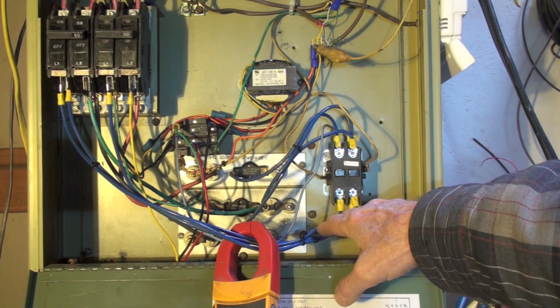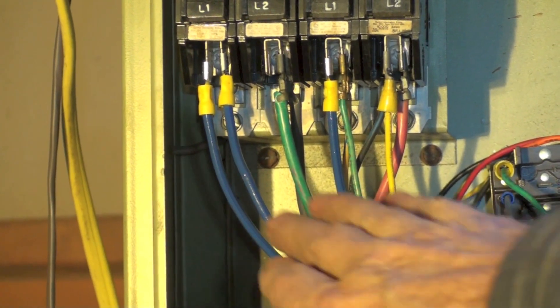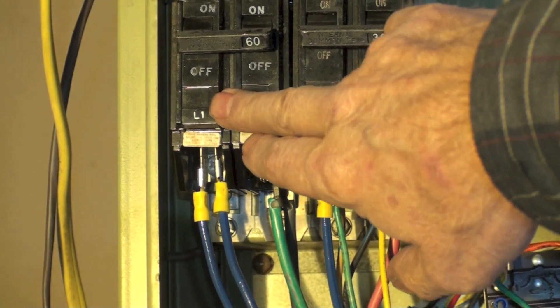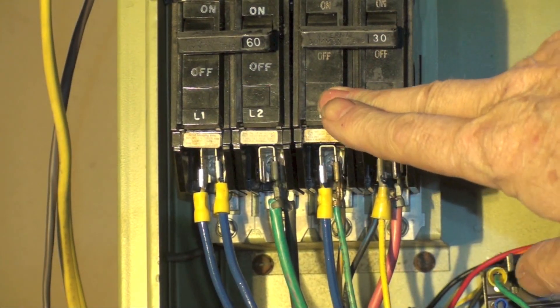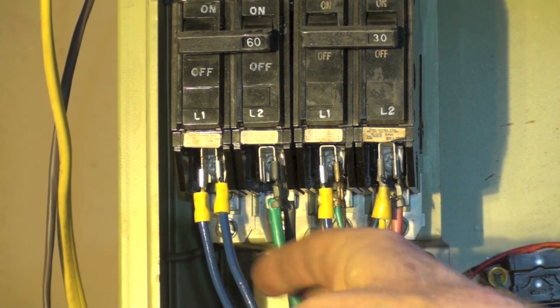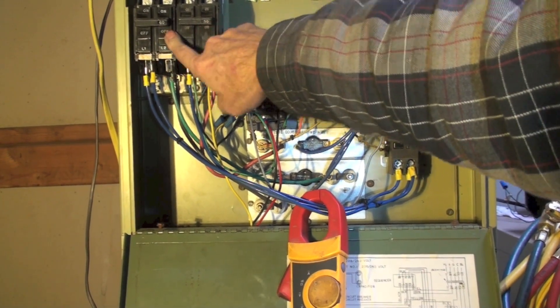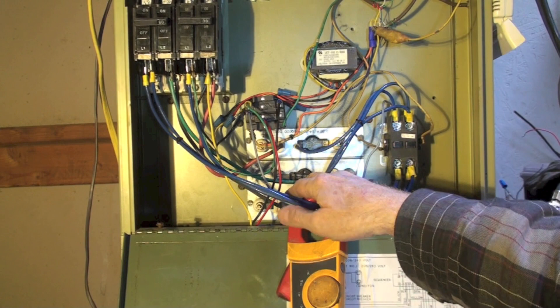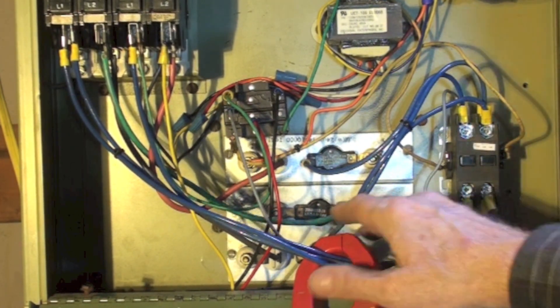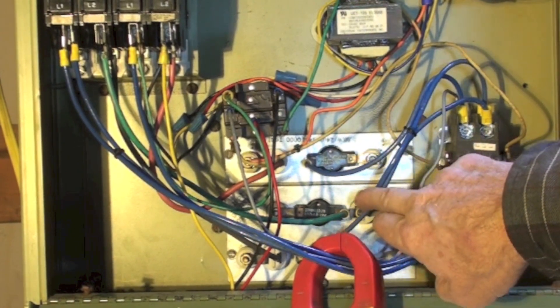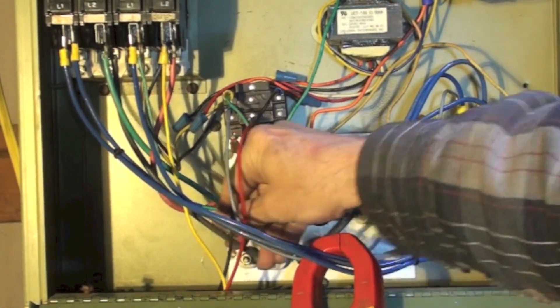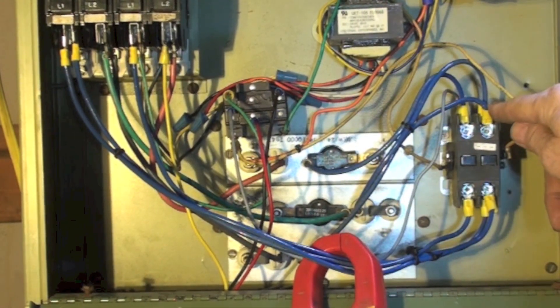Make sure when you do this contactor, one of the things about it, because I have two elements running off of one set of contacts here, go over to your breakers and be sure those two wires are going to the same side. Like these are both going to L1. Be sure the two are going to the same terminal, like it's L1 right here. Now this is one breaker right there, there's another breaker right there. We don't want anything mixed up between the two breakers. So if I was to take the wires that came off of here, now there's two wires coming off there, so if I go to L2 and that same breaker, I have a wire here and I follow it down and it goes to here. That goes into that second element, then it comes out of the element right there, goes over to this side. And if I go to the bottom one I have the same thing. I have a wire coming from L2 on this breaker going to here, coming out and going to the same side.